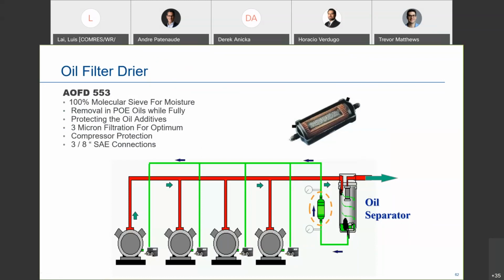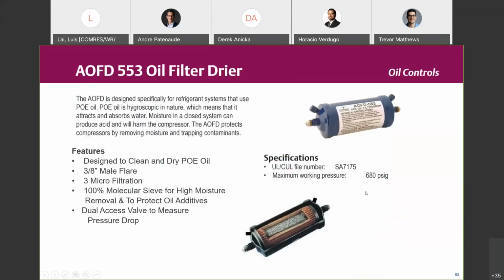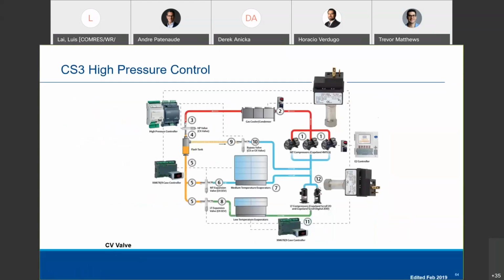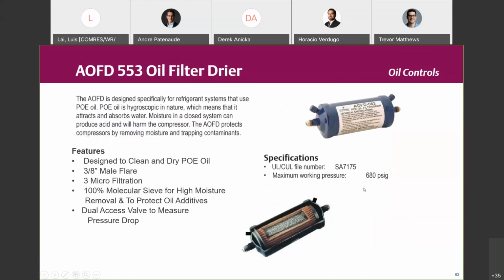Some of them are a bit acidic for protecting purposes. So you don't want a filter dryer that'll strip the additives out of the oil. So that's why we put 100% molecular sieve for moisture in that. And the outside is a 3-micron filtration, and we need that. So it is rated to 680 pounds, and for oil systems, that's generally plenty of pressure.